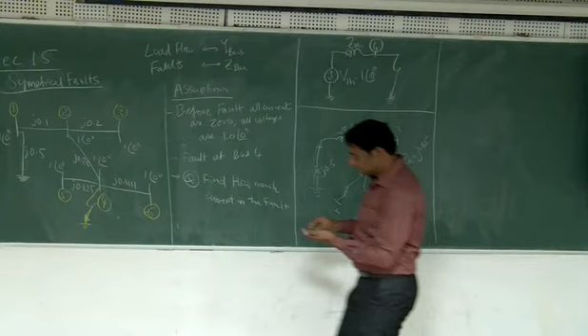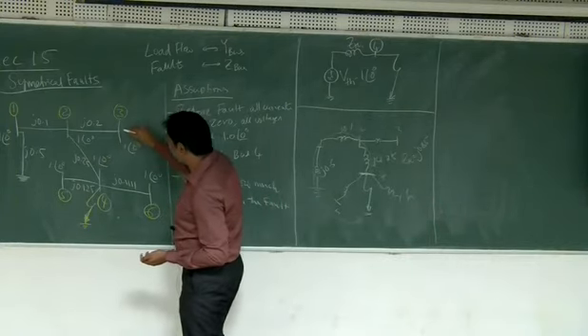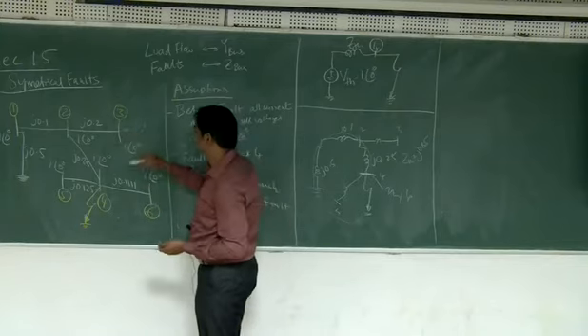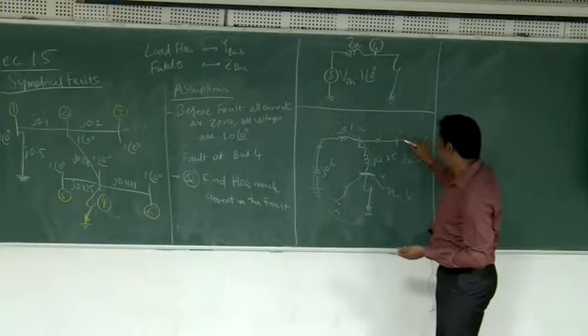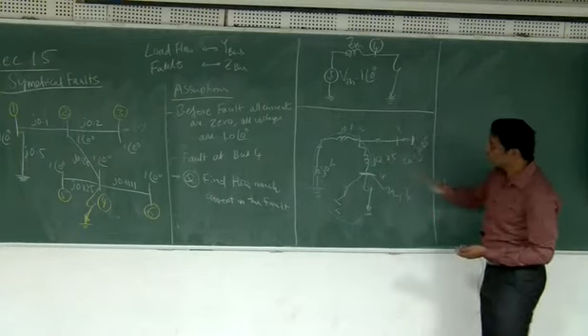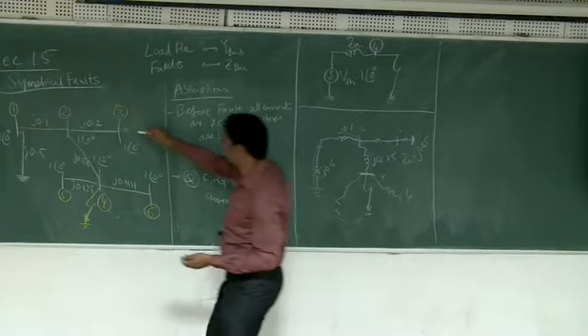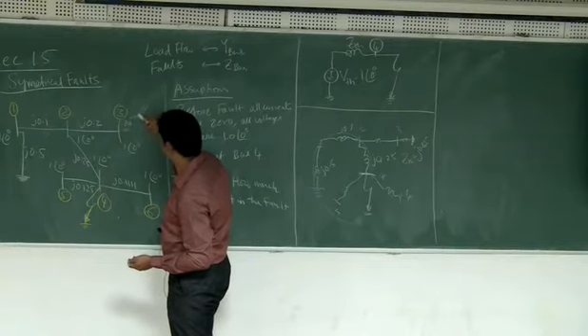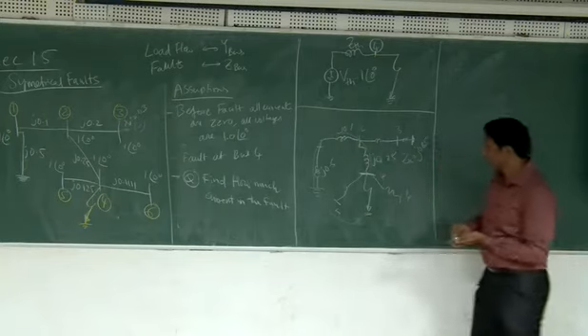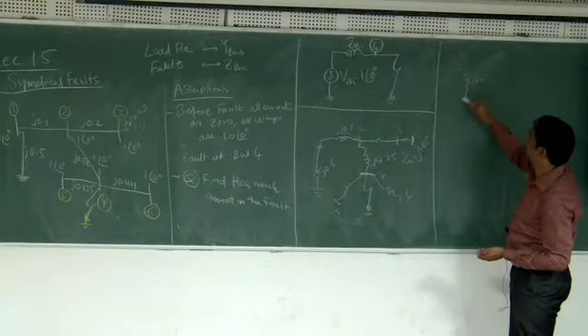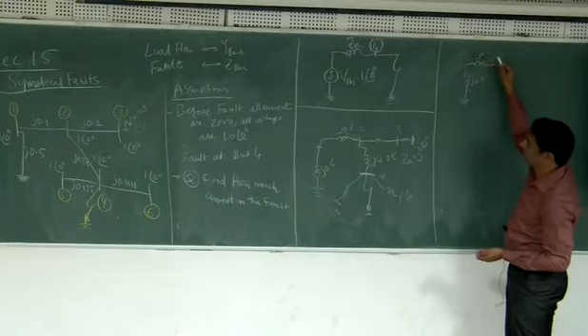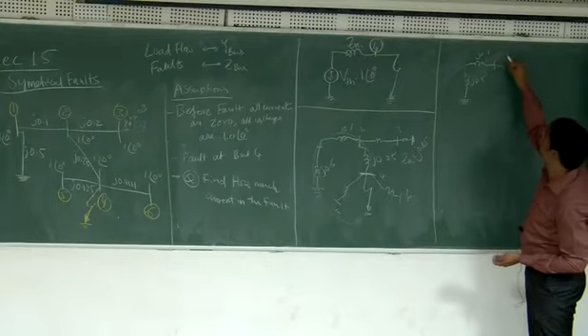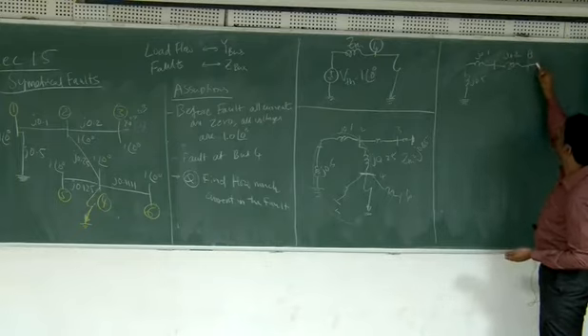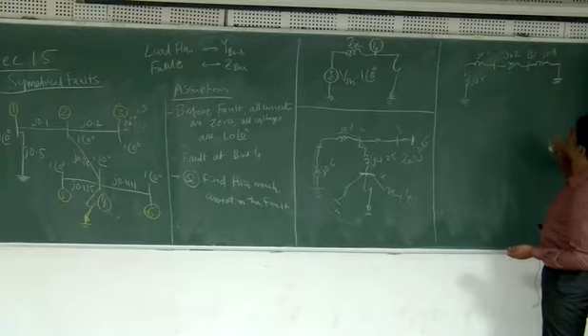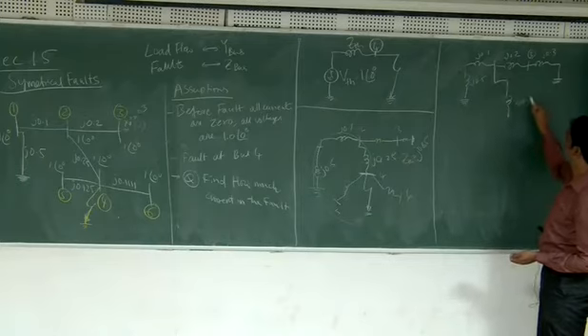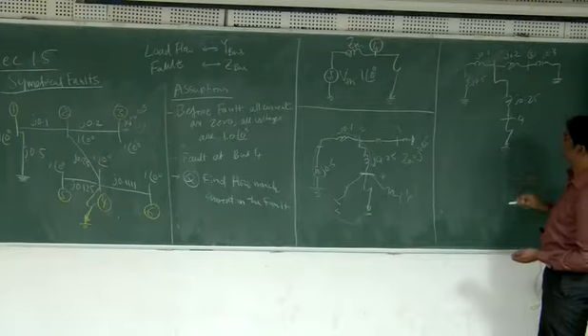Now what if I consider a machine here, a generator? Some impedance has to be given. If it is given, then you can consider here a machine with an impedance and then short circuited. Then how will you solve it? Let's say this impedance X_d double dash is 0.3. The circuit will be like this: J 0.5, grounded, then J 0.1, then between 2 and 3 it is 0.2, then there is bus 3, here there is J 0.3 and this is also grounded, and here there is J 0.25 and this is bus 4, and there is a fault here.